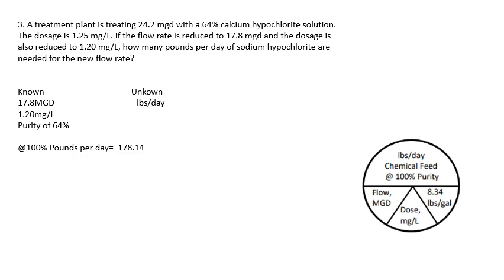But remember, this is at 100% purity. To solve for purity, we divide because we're solving for the amount above 100%. Divide by 64% as a decimal: 178.14 pounds per day divided by 0.64 gives you 278.3 pounds per day of the 64% calcium hypochlorite solution.